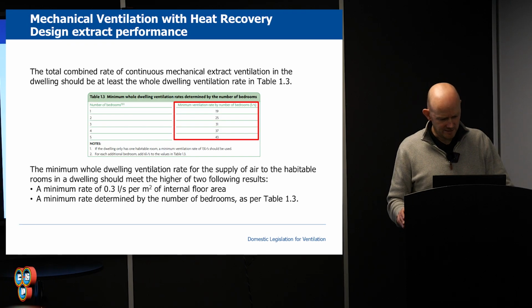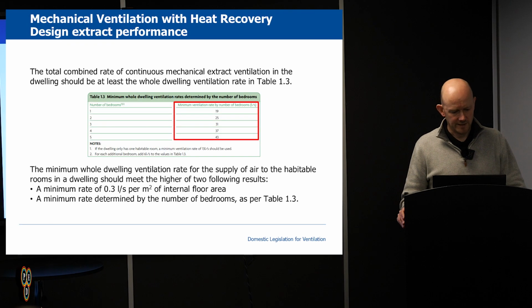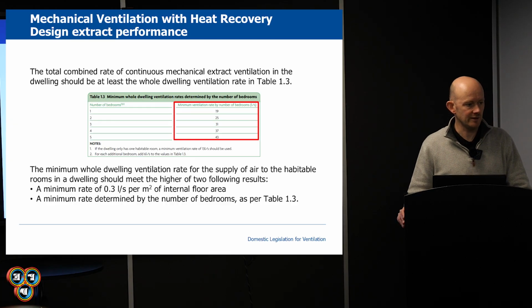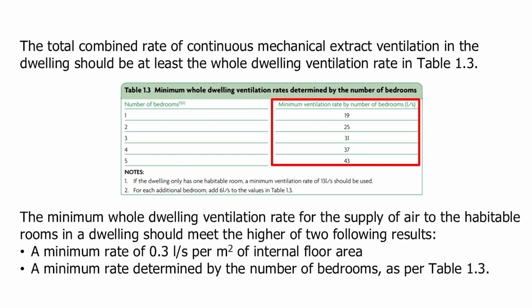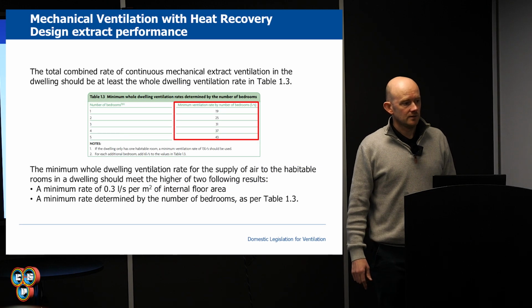This slide's been repeated from earlier about calculating bedrooms and how many litres of air are needed for a property. For mechanical extract ventilation, the continuous supply and extract rate has been calculated in 2 ways, and the larger of the 2 volumes will be used. You can see how it goes up as the bedroom numbers go up. So for that 5 bed, what they're saying is those 5 bedrooms need 43 litres a second, split across 5.